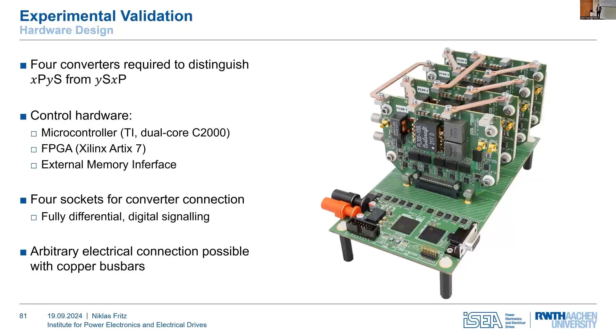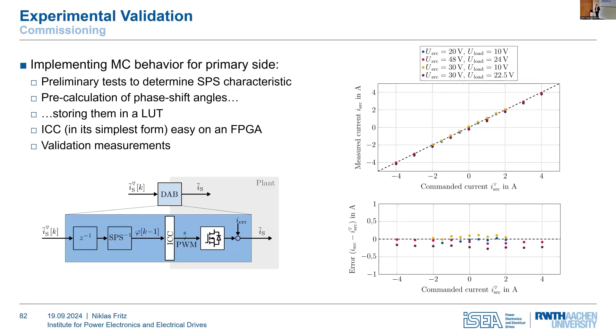The first thing to check is whether this MC-type port, for example on the primary side, actually behaves nicely like an MC-type port. I implemented open loop current control for the dual active bridge to see how it replicates any commanded current. I took a measurement with commanded current on the x-axis and actual measured current on the y-axis, and they're very nicely aligned. Plotting the error shows it's always less than 400 milliamps, which isn't perfect since it's open loop, but it's still nice. The first takeaway is that ensuring this port really behaves like a good MC or MV type is critical to the performance of the decoupled control.